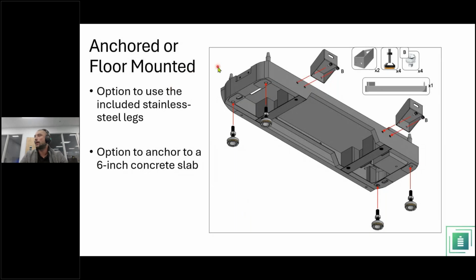All right, so floor mounting can be anchored or floor mounted. Anchored, you would use the included bolts that anchor into a 6-inch concrete slab using these holes right here. But if you're not using a concrete slab, and let's say you're installing this in somebody's garage, then you would use the included stainless steel legs. Not to say you can't use the stainless steel legs outdoors, just make sure everything is leveled, because that could create some conflict with the orientation of the battery and cause issues during installation, like the holes not aligning, etc.